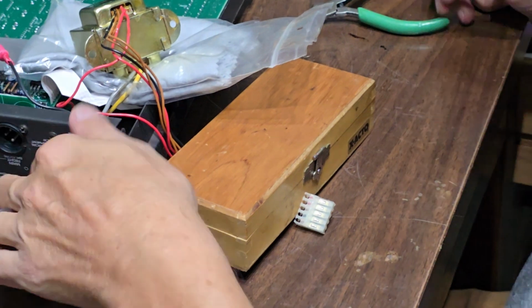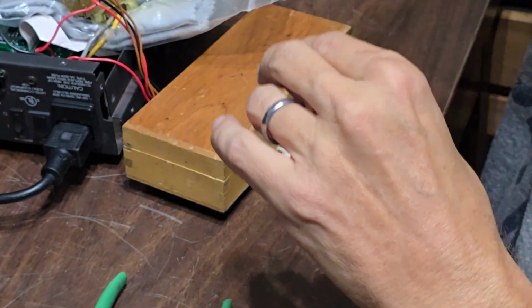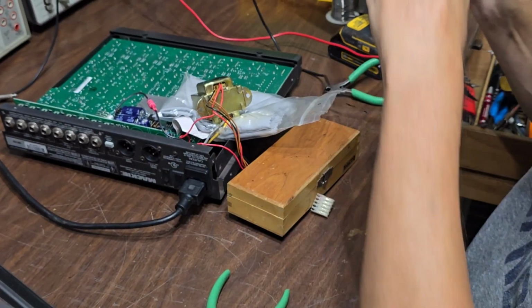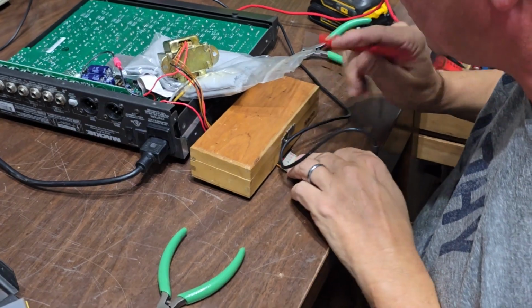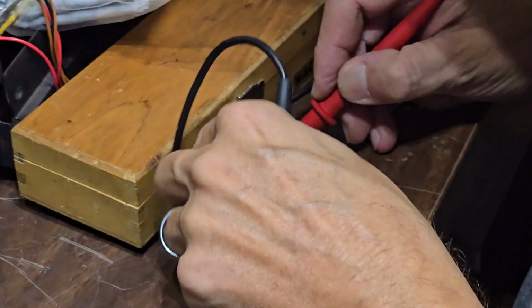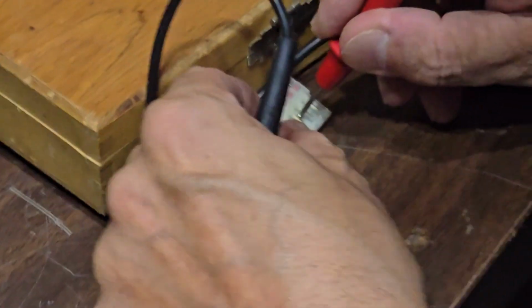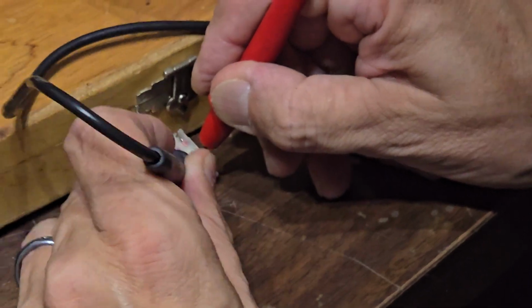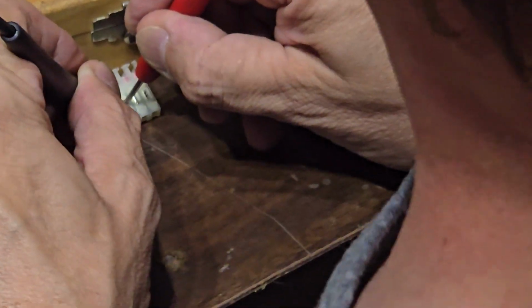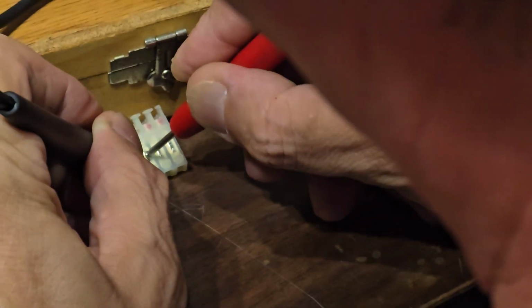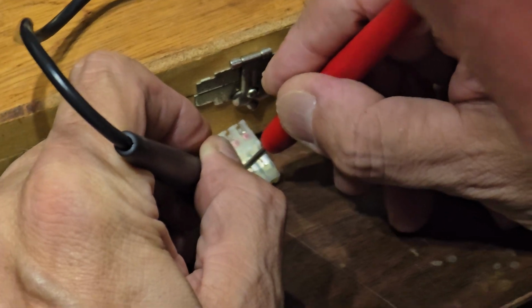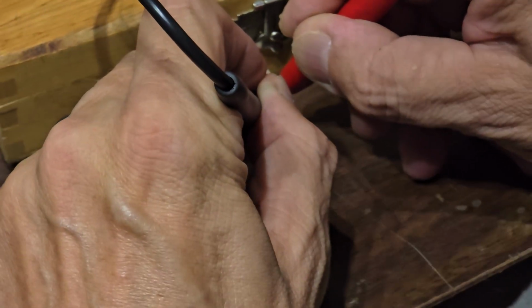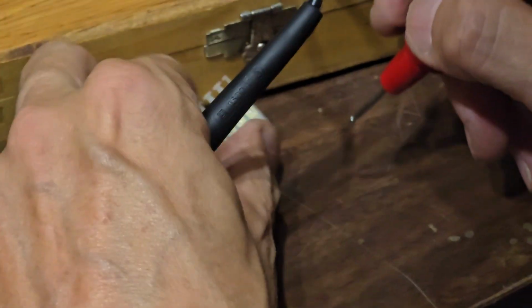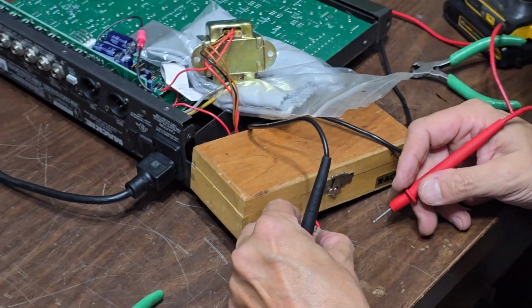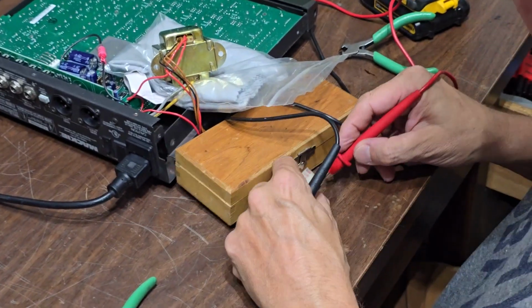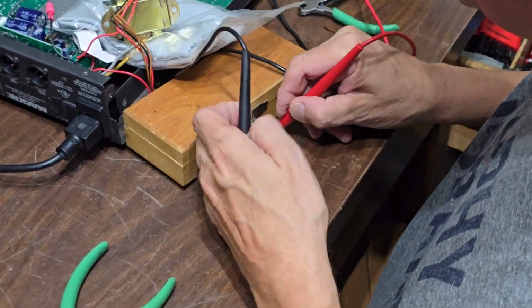I'm going to turn it back on. And I'm going to take my meter and go straight across those secondaries and see what I can see. So from brown to brown, I would totally expect there to be some voltage if it were unloaded. And I'm measuring flat, nothing. Now, from brown to black, nothing. Now, if I look over here at this red tap, this is two sides of that.